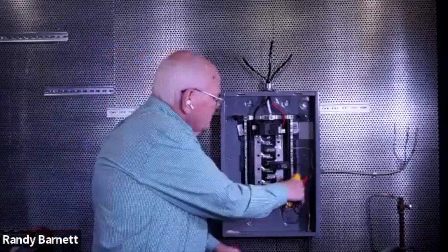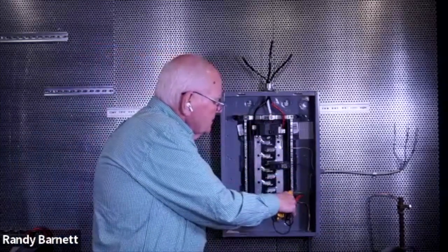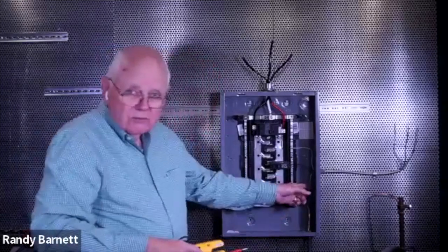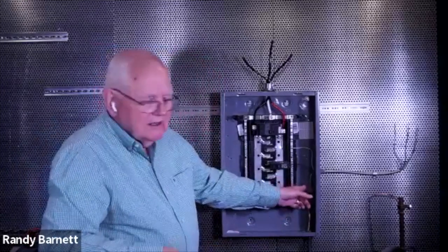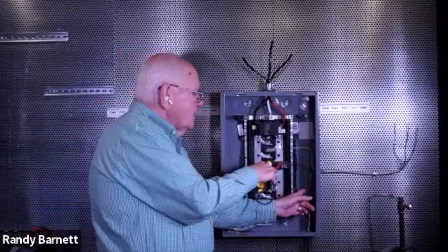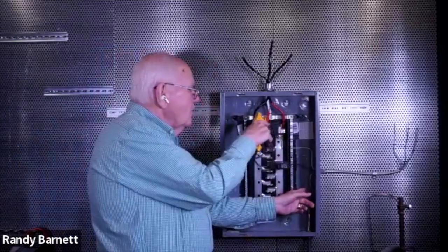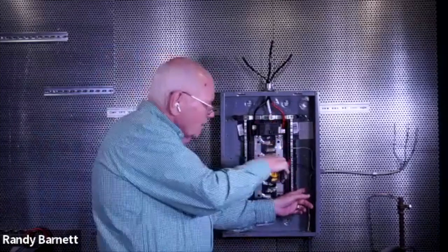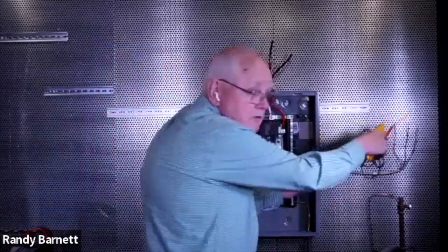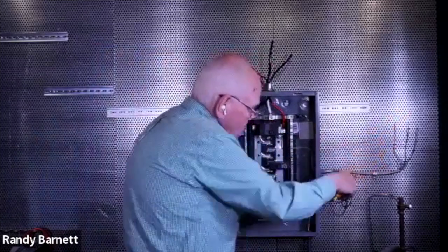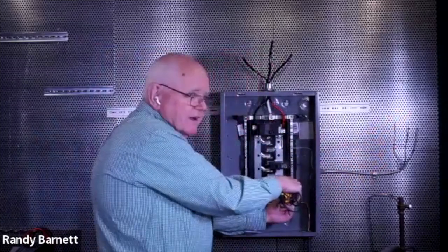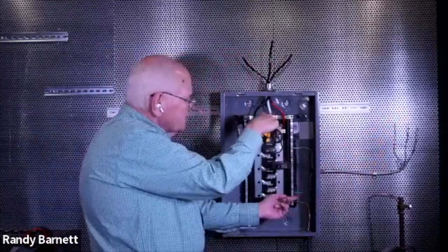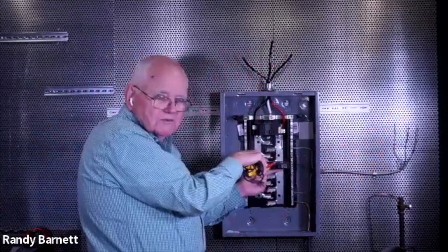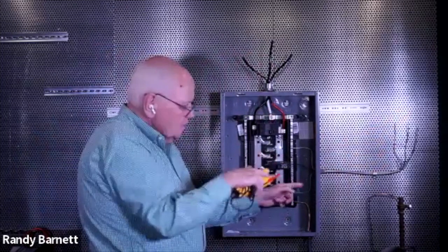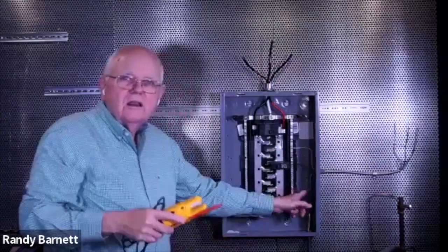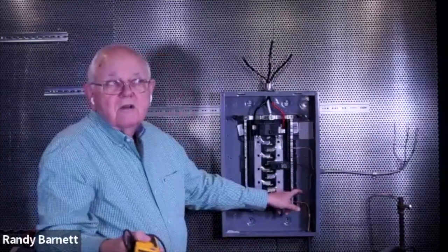Now, the equipment grounding conductor down here, the green wire. Equipment grounding conductor, okay, if you think about it, we said that the circuit breaker is what's going to interrupt the current flow in the event of a ground fault, right? As the current flows on the ungrounded conductor, goes into the frame of the equipment, which we don't want, of course, it returns back on the equipment grounding conductor, the green wire down here, and goes back to the transformer. The circuit breaker trips and clears the fault. So what size do we want the green wire, the equipment grounding conductor?